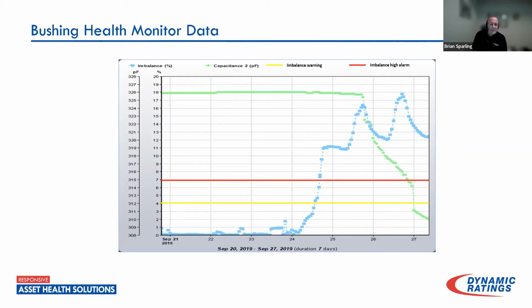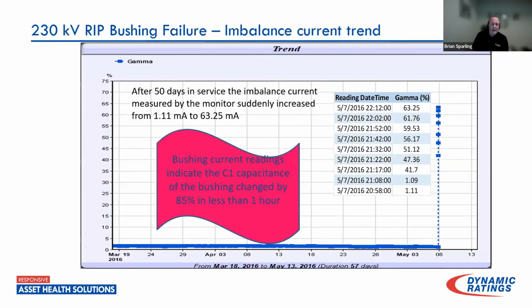That's OIP bushings. With RIP, we didn't expect to see the same sort of failure condition, but we were all surprised when we captured a bushing failure of an RIP bushing in service. Here is the trend of data. This monitor was installed back in 2016, and after 50 days in service, the imbalance current measured by the monitor increased from just over 1 milliamp to 63 milliamps in an hour. This reflected an 85% change in capacitance in less than 1 hour.